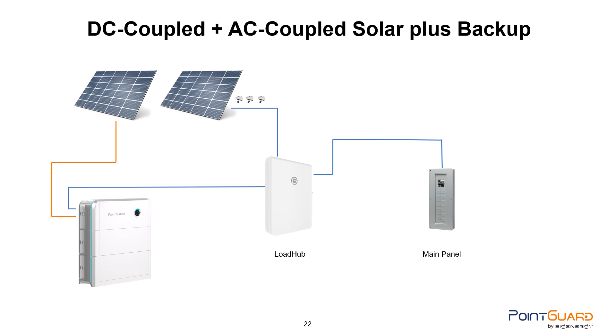And yes, PointGuard Home is able to accommodate both DC coupled PV and AC coupled PV arrays in the same system. This allows you to go back to your PV only customers, add a battery, and upsell and upgrade the PV system to add another array. The existing array would AC couple to the load hub, and the new array can simply be connected to the controller.